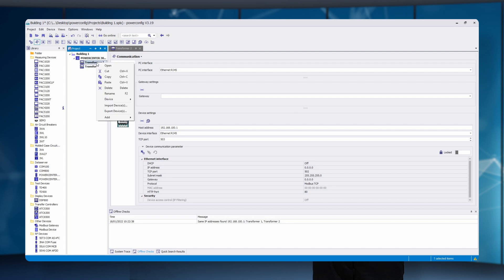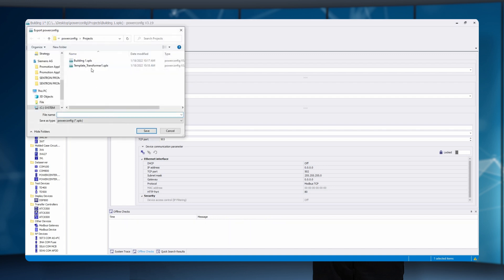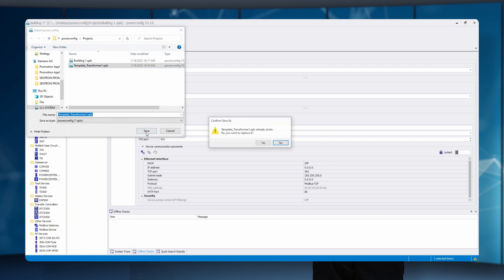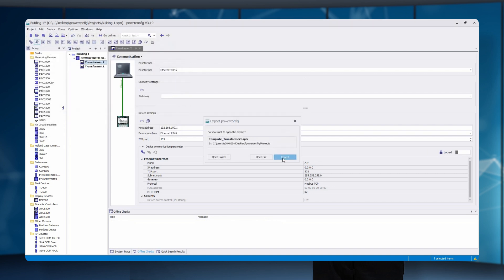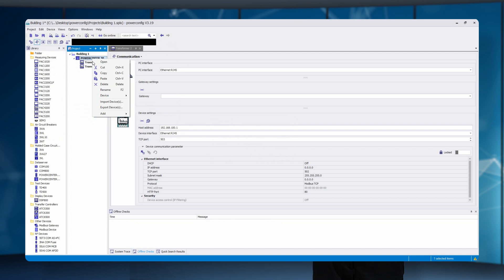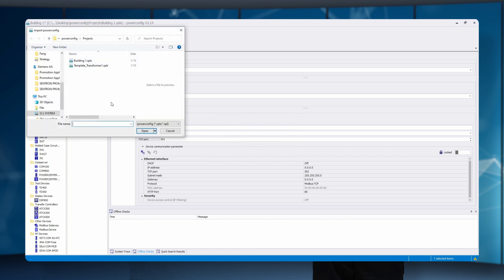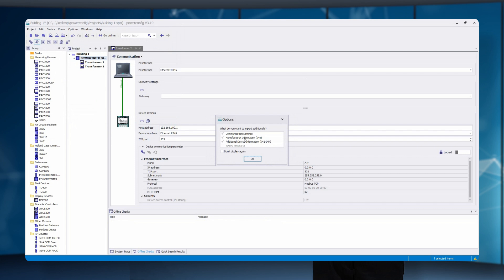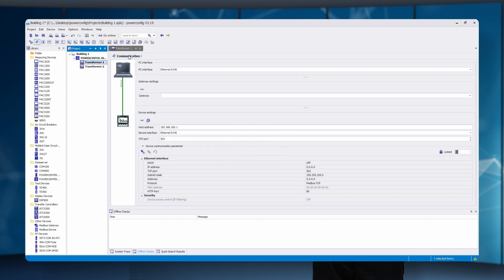The second method is the import/export function. Existing devices, for example from other applications like SIMARIS design, can be taken over including protection parameters. Or already stored devices can be inserted with the import function. To do this, select the required device and right click to export it and save it as a template with all the data entered. In order to use it again, click on the project in which it is to be integrated and select the import function. A pop-up window appears with the question whether all values are to be taken over.